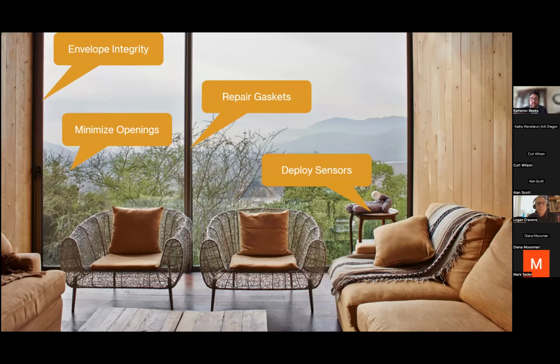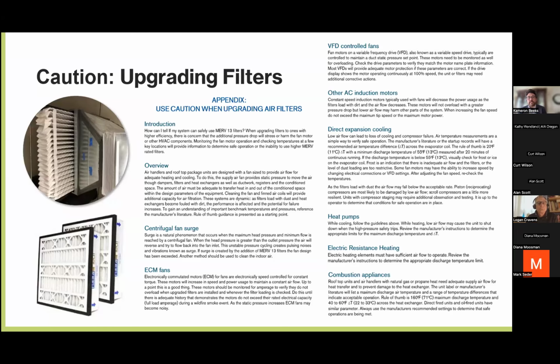Here's the caution I was talking about as far as upgrading filters go. Fans only have so much static pressure capability - they can only push so much air against so much pressure. When you add filters, they tend to add pressure to the system. I'm not going to go through each of these warnings, but ASHRAE has outlined several concerns when modifying existing systems with additional filtration, just to make sure we don't create other issues elsewhere in the building.